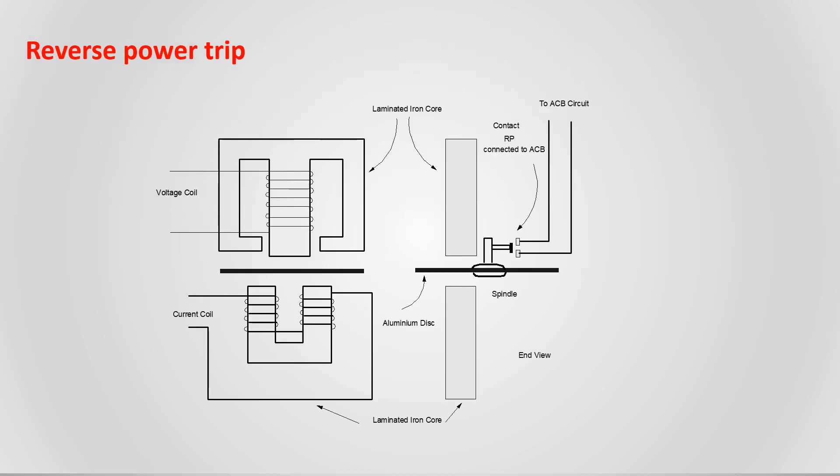Reverse power trip: We will do the testing of reverse power trip when two generators are running in parallel. Put the control of the testing generator in manual and also governor in manual mode. Adjust the governor in anti-clockwise direction, that is, lowering the load and shifting the load to another generator. At the set value of reverse power trip setting, it will open the breaker.